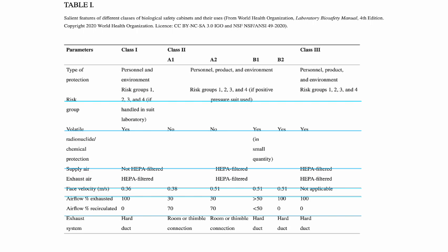As you can see here, in terms of type of protection class, the lowest class of biosafety cabinet, your Class 1, can only protect the personnel and environment, while your Class 2 and Class 3 can provide complete protection. They can provide personnel, product, and environment protection.